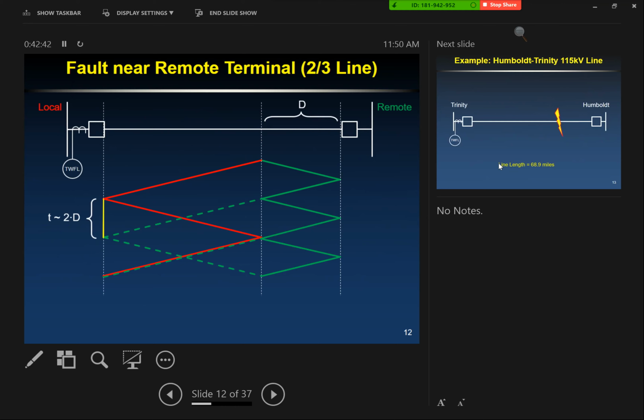So again, it's proportional to twice the distance, but now we're looking at your fault location given with respect to the remote end and not your local end. We will look at the polarities. We know this polarity will be opposite this, because it's a remote end reflection, whereas before the polarity should be the same. So that'll help us in the event analysis.